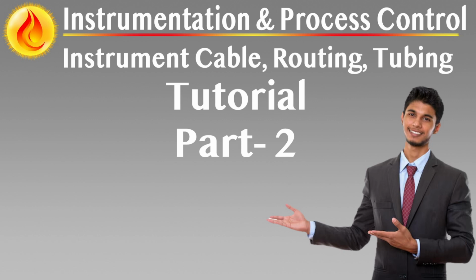Each instrument cabinet and MDF must be connected to the instrument earth bar via a dedicated color-identified cable with a minimum cross-section of 6 mm squared. Terminals for these connections must use yellow-black insulation and be clearly marked with the associated cabinet or MDF number. All earthing bolts must be a minimum of 10 mm in diameter to ensure mechanical integrity and low resistance contact.